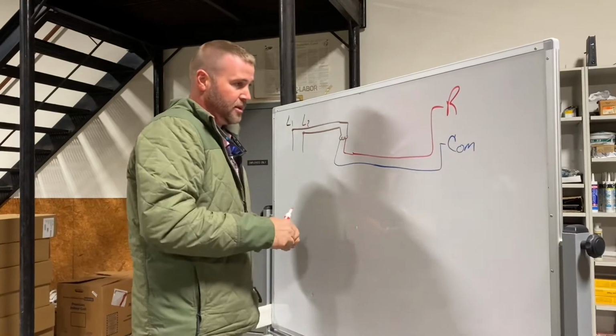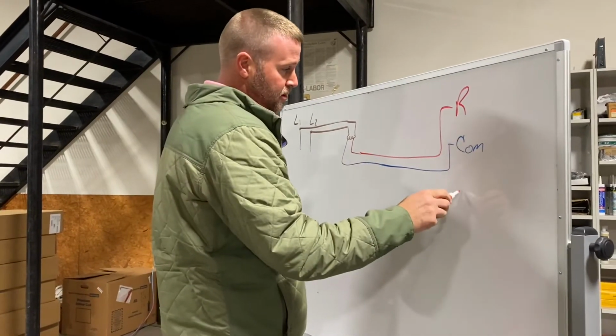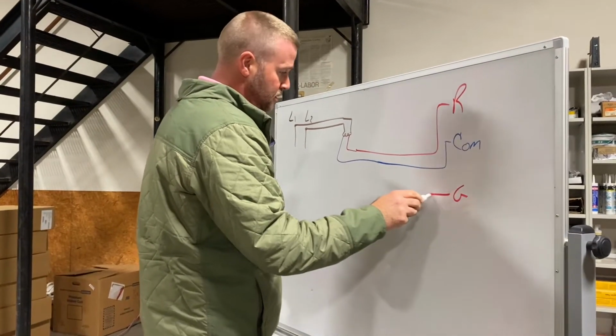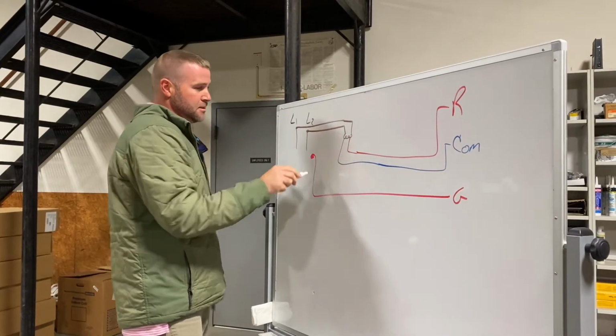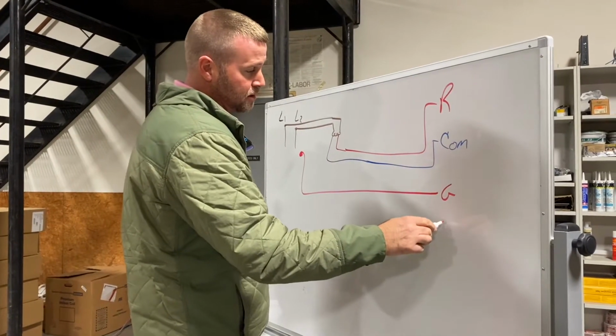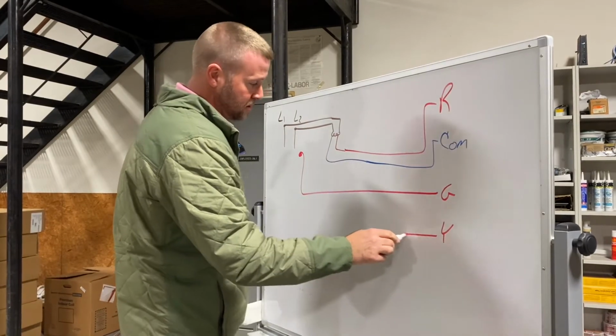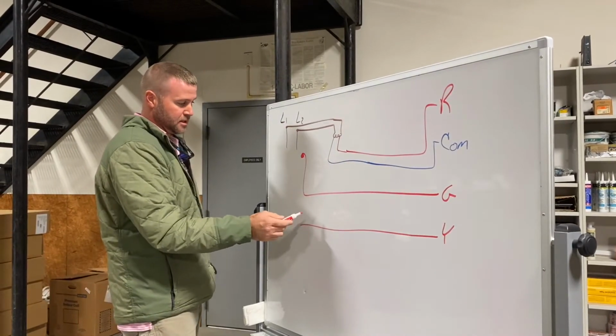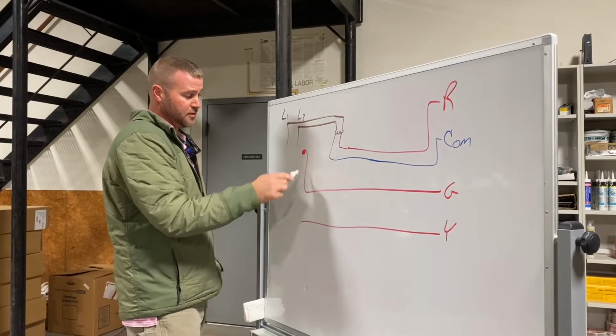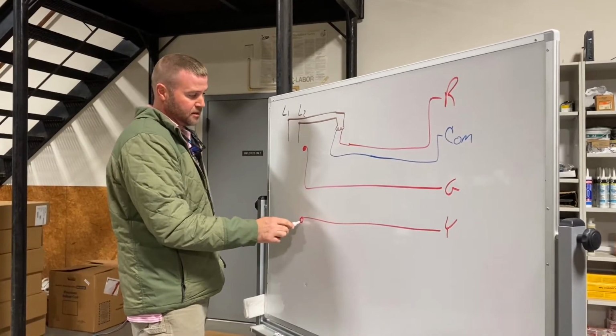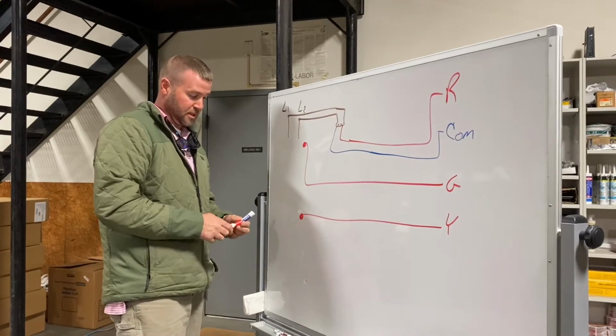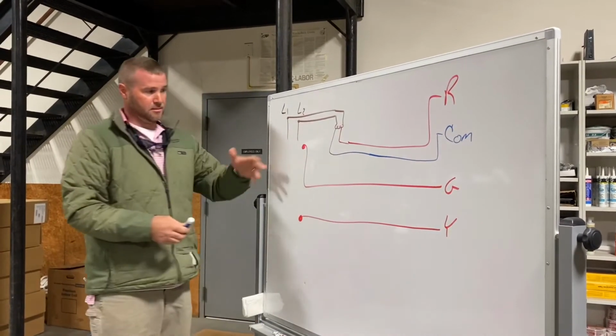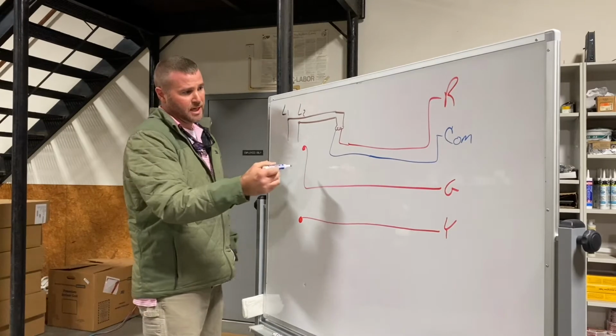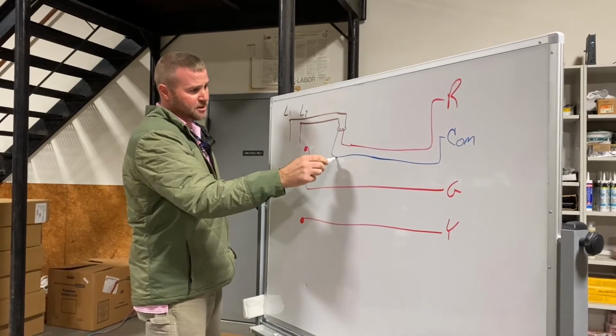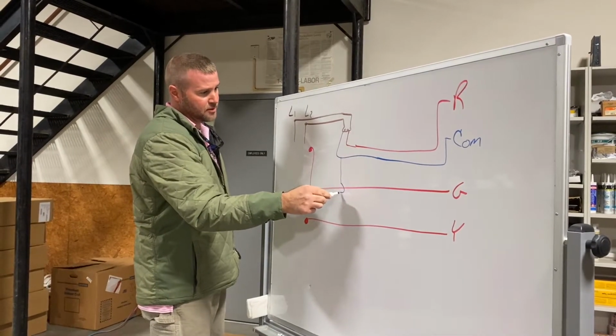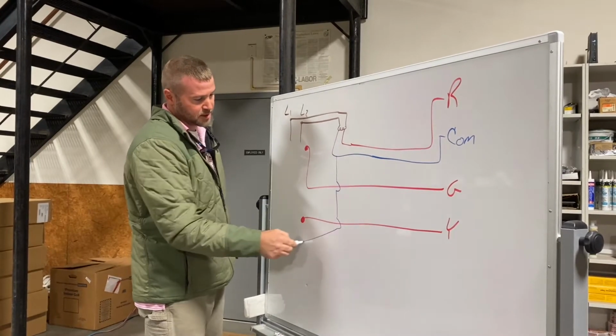And then from there, let's take our G terminal back to this contactor, and let's take our Y terminal - actually we'll take our G to a fan relay, and our Y to the contactor. Now that's at its base, that's what we're going to have, but what we know from experience is that we also have to have this common at each one of these devices.